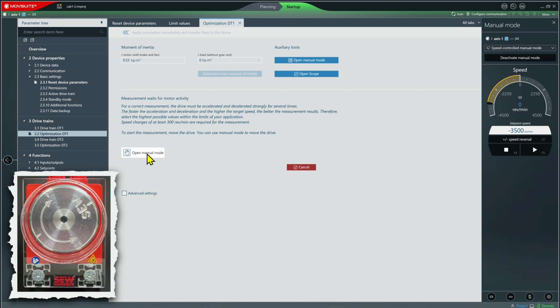Well, yes it is, but I want to change to a different version of manual mode that is used for tuning. Notice when I click this, it changes to what's called Load Cycling Absolute Mode. In this mode, MOVISUITE is going to cycle the motor back and forth, and by doing this, it's going to be able to determine the inertia by measuring the jerk as it changes direction. Now I need to do a few things first to get this set up.